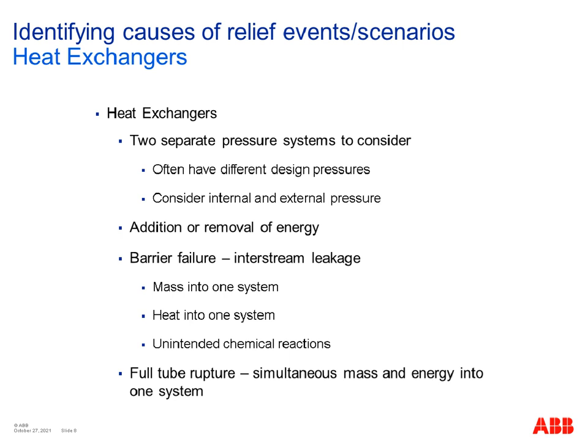Then you can get mass flow from one system into the other, heat flow from one system into the other, and you could have things happening like unintended chemical reactions when those streams come into contact with each other, which was never part of the design intent. And in a full tube rupture, you'll of course get mass and energy going from one side of the system into the other, assuming they are at different pressures.